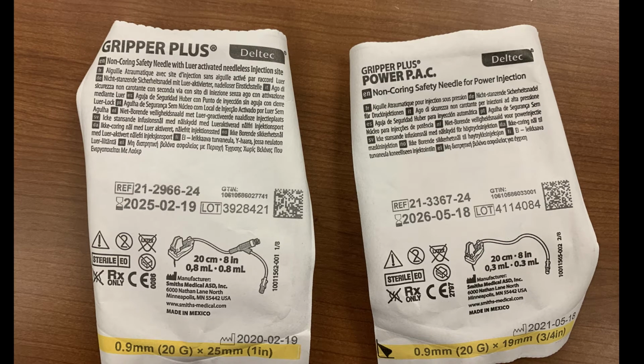Some implanted ports are power injectable, which means that fluid can be pushed very quickly into a port with intense pressure, and the port will not be damaged in any way. This is important for some procedures such as CT with contrast, because the contrast dye must be injected in this manner. A power injectable port can handle this pressure easily. However, other ports are not designed for this level of stress and would be damaged or destroyed by the process.